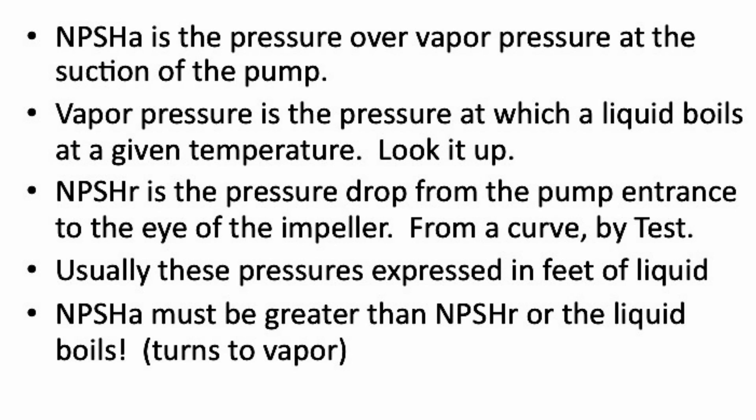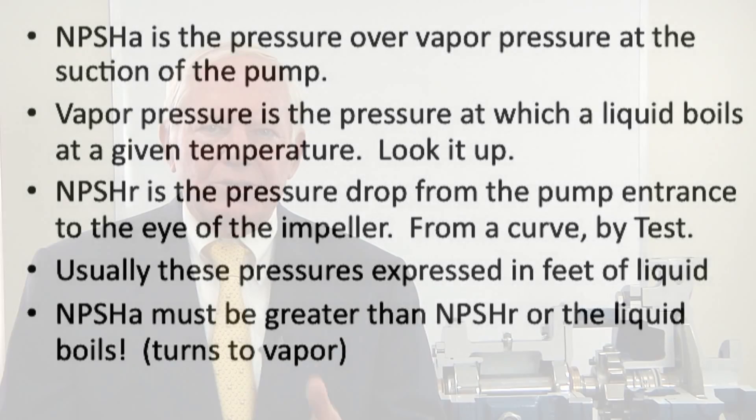If NPSHA is insufficient, this will cause a reduction in performance, and also when the pressure in the pump decreases below the vapor pressure, the vapor bubbles will collapse causing noise, vibration, and damage to the pump. This is called cavitation.